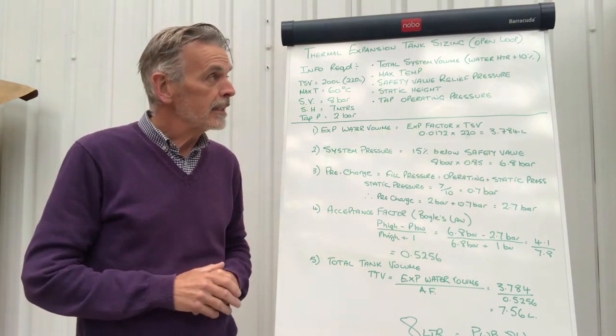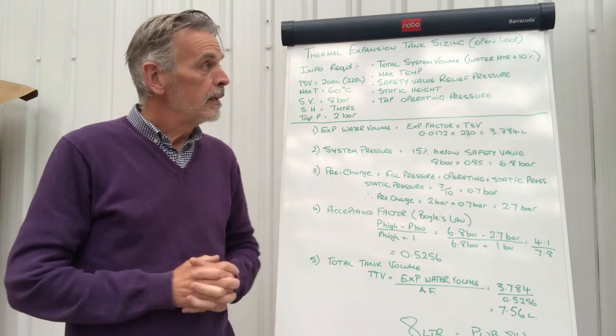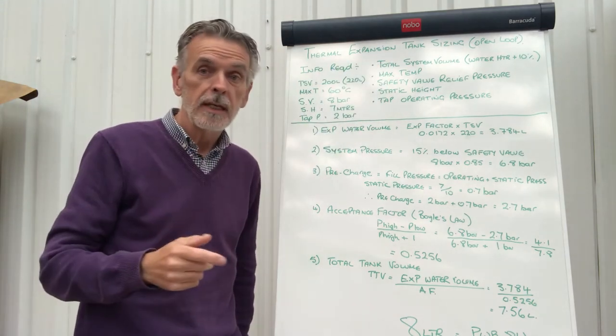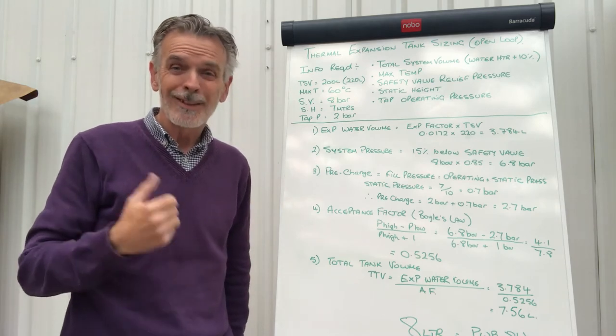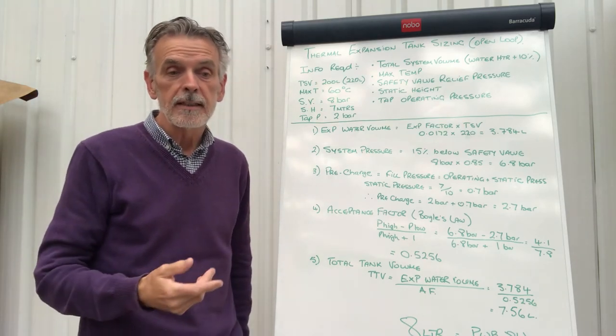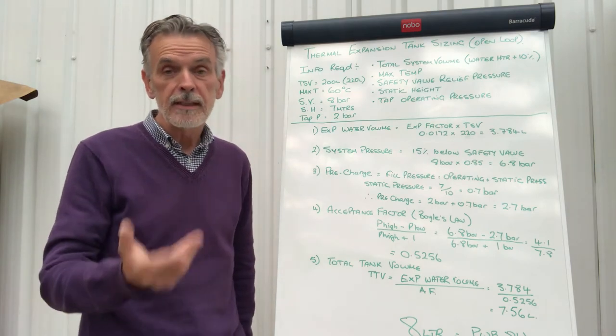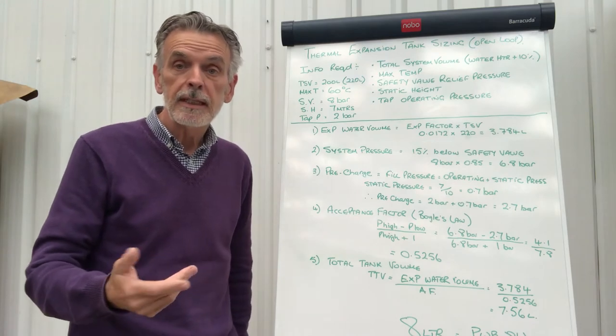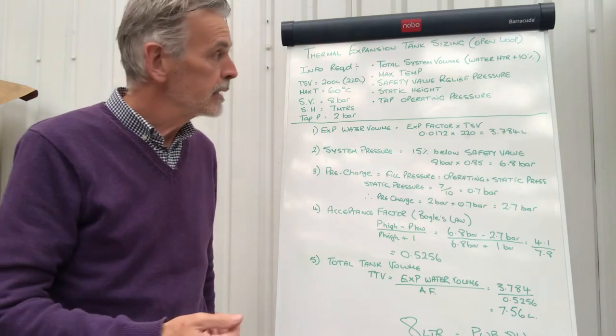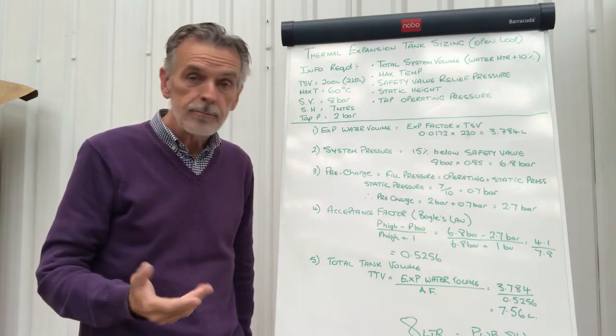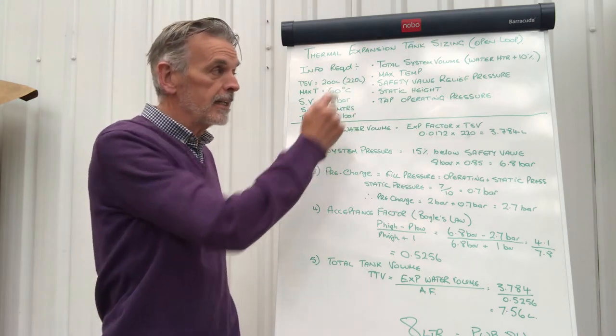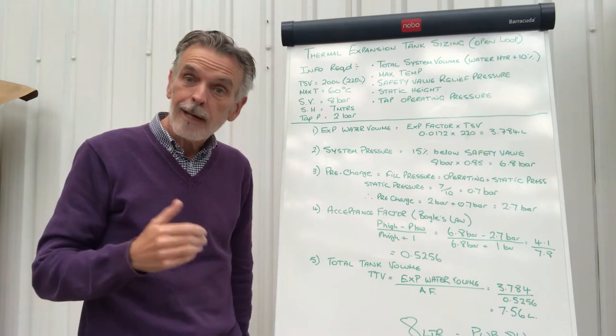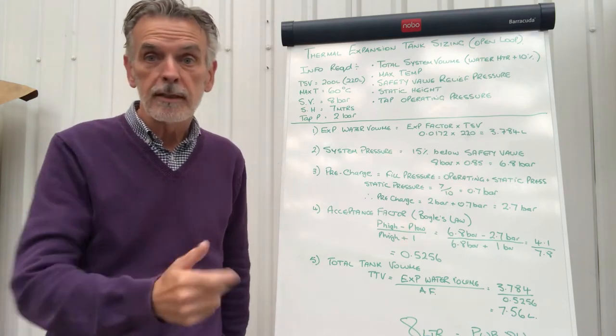So the first thing we need are some basic parameters: the total system volume of the water in the system, the quickest and simplest way of calculating this is the calorifier size or unvented cylinder size plus 10%, the maximum temperature that you will be storing the water at, the safety valve relief pressure, the static height to the highest discharge point in the building, and the tap operating pressure that you require at that particular point.